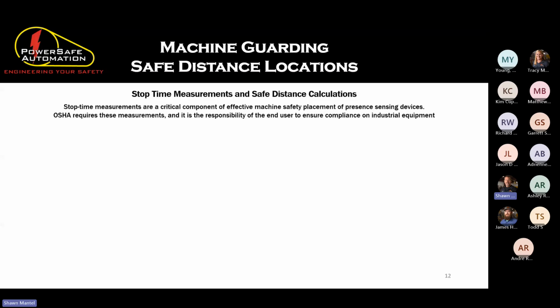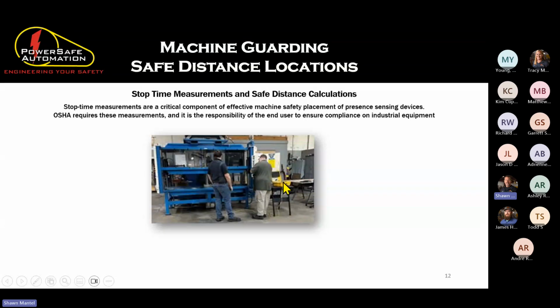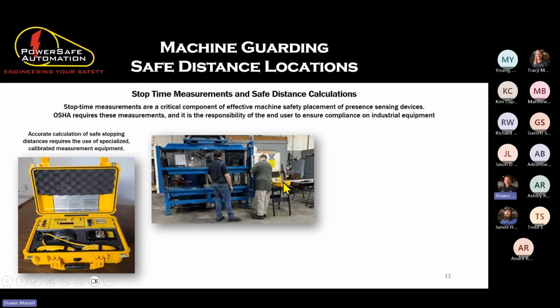So if you have physical guarding and you run at it, you're going to get stopped. If you run at light curtains and break through it, it's not going to stop you - you're in there. So you have to make sure you're using the right tools. To do that, you want to use some sort of stop time measurement tool that you can put on the machine to give you what that is.